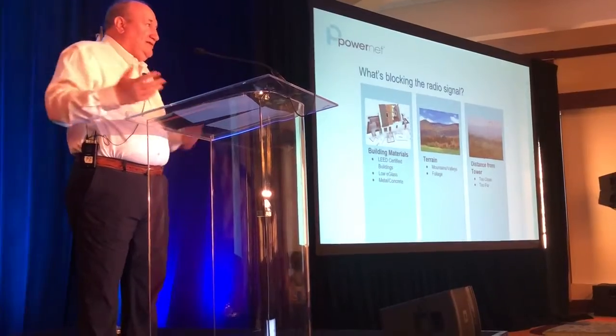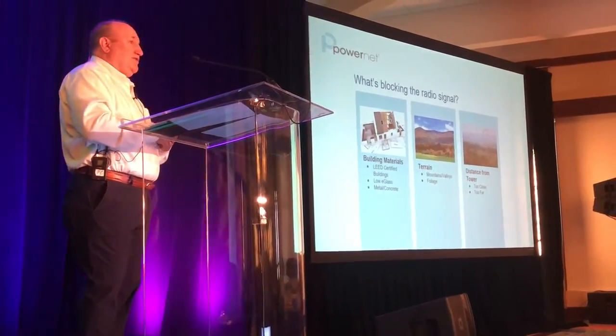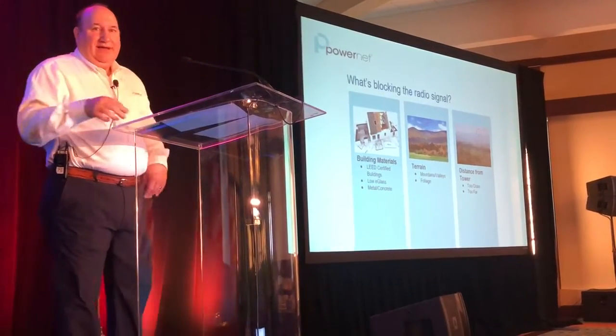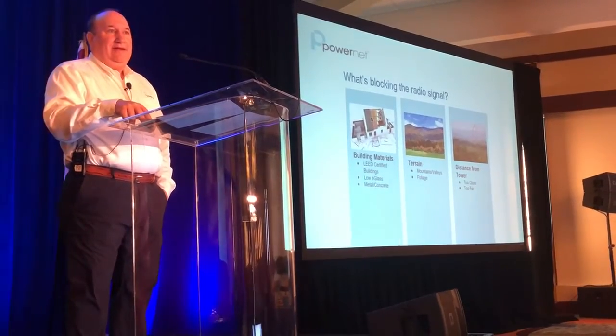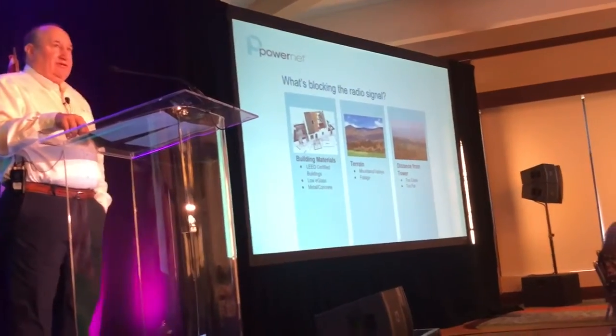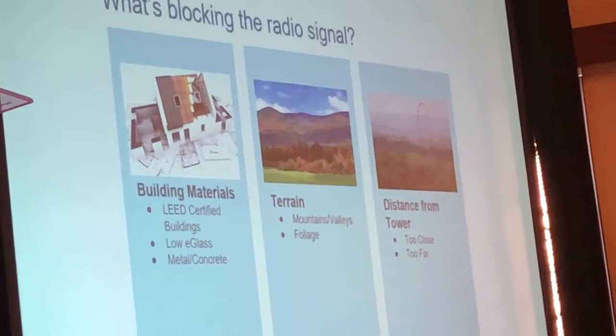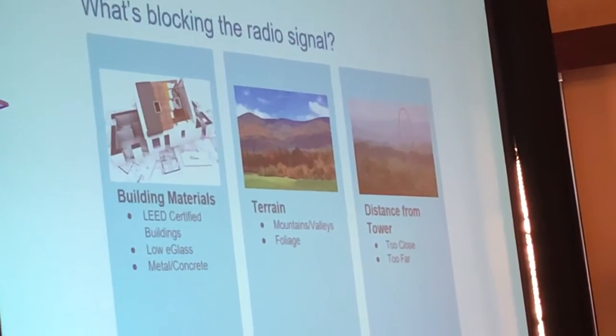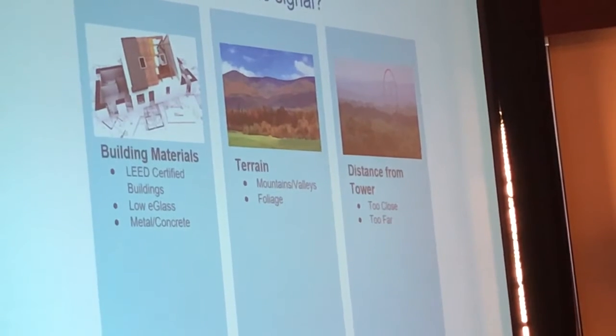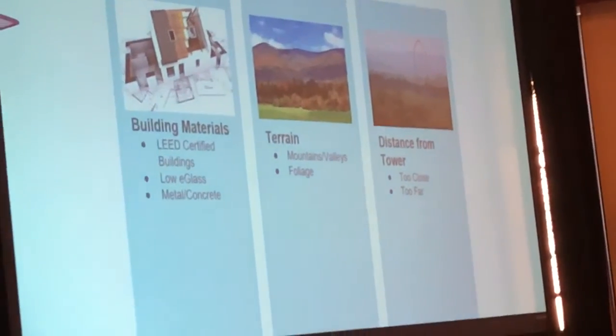But what's all of a sudden causing the need for these more? You're going to hear about it a lot more, especially in Florida. Things are getting more strict here. In fact, this year, Florida updated their building code. It's chapter 633, section 202, paragraph 18, and it's for high-rise buildings. That's what they're addressing right now. High-rise is anything where a residential floor is more than 75 feet above the lowest area that a first responder would enter your building.